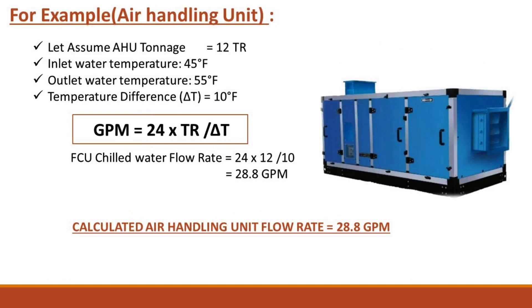For example, consider an air handling unit. Assume the AHU tonnage is 12 TR, with an inlet water temperature of 45°F and an outlet temperature of 55°F, giving a temperature difference ΔT of 10°F. Applying the formula: GPM = 24 × TR / ΔT = 24 × 12 / 10. The calculated air handling unit chilled water flow rate is 28.8 GPM.